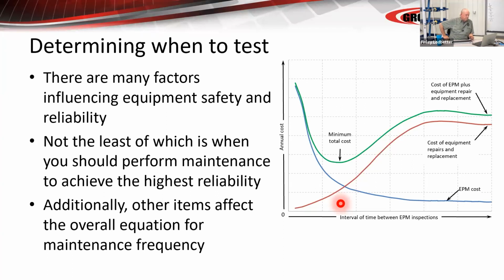You can spend $150,000 on a big weekend shutdown, anywhere from 3,000 to 150,000 and anywhere in between. That 150,000 is inconsequential if you lose a section of gear. That section of gear smokes up the 2 adjoining sections, and at the same time shuts you down for 3 or 4 days while you're acquiring the gear, bringing it in, putting it back together, and getting the plant back up. So there is a situation where there is a diminishing return. When you get out to about 3 years, 4 years, it really becomes, financially, a question of hit or miss and what you want to do.